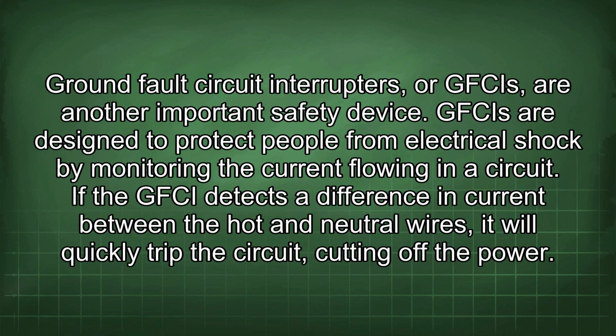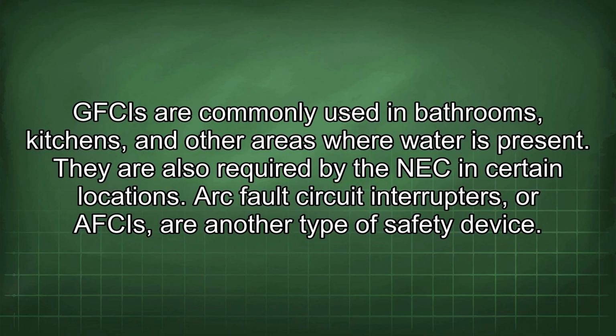Ground fault circuit interrupters, or GFCIs, are another important safety device. GFCIs are designed to protect people from electrical shock by monitoring the current flowing in a circuit. If the GFCI detects a difference in current between the hot and neutral wires, it will quickly trip the circuit, cutting off the power. GFCIs are commonly used in bathrooms, kitchens, and other areas where water is present. They are also required by the NEC in certain locations.